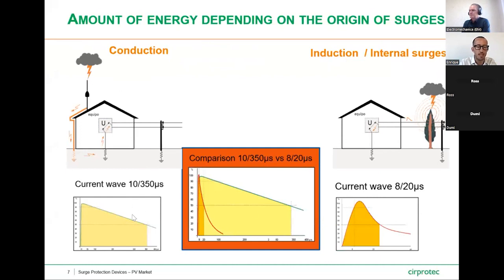That's correct, yes. These are the current waveforms the IEC standard set up in order to simulate the amount of energy coming from the different origin of sources. So in the case of conduction, when we do have direct lightning impacts in our installation, the standard set up a waveform named 10/350 microseconds, which means that in 10 microseconds we are getting 90% of the total amount of energy, and then in 350 microseconds it's reduced by 50%. Then, in the cases where we do have sources coming from induction or internal sources, the waveform stated by the standard is the one named 8/20 microseconds, which means that in 8 microseconds we are getting 90% of the total amount, and then in 20 microseconds it's reduced by 50%.